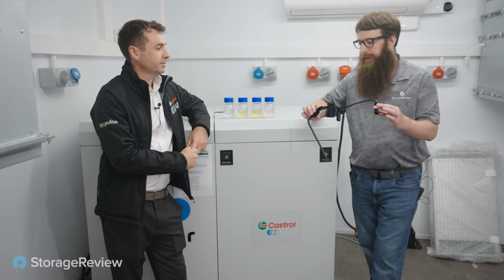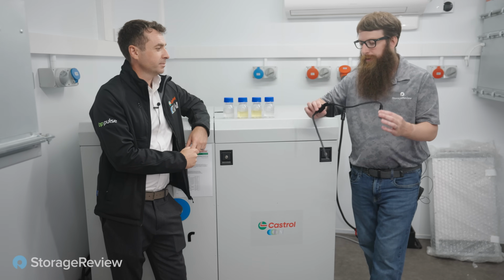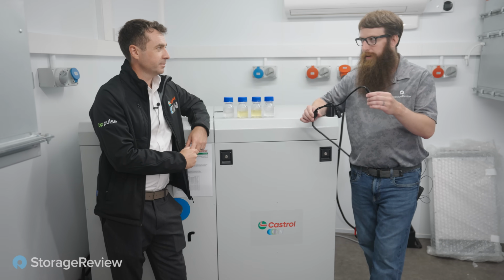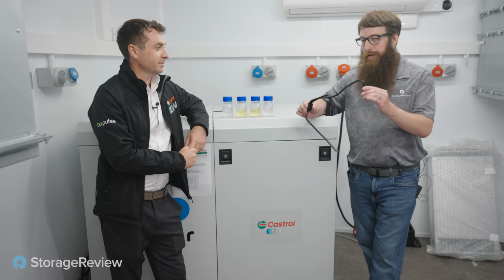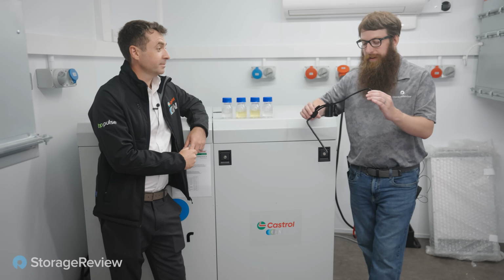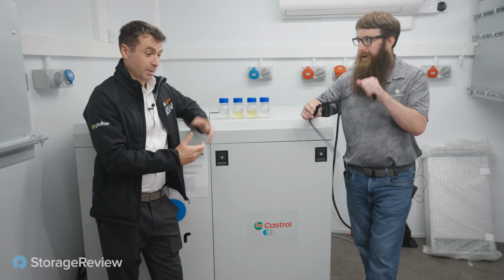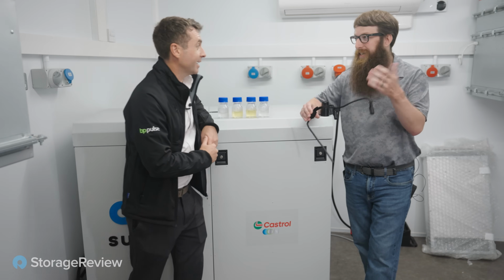So if someone had an incompatible fluid and went to unplug their power supply, even though the fluid might not be conductive and shorting it out, they could be grabbing line voltage. Potentially, yeah, and that's a bad scenario - that'd be a bad day.